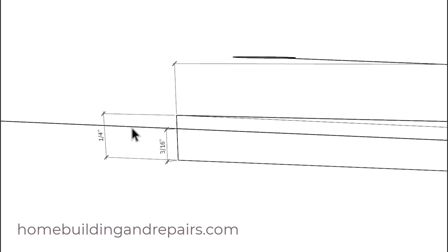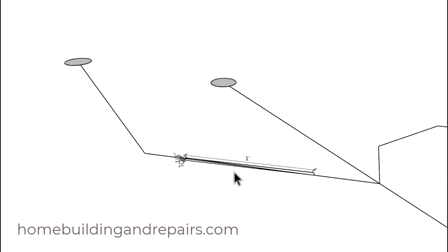So in 12 inches, this line right here, the line of the pipe, isn't a quarter of an inch per foot. I repeat, it is not a quarter of an inch per foot and could actually create a problem with your building inspector.